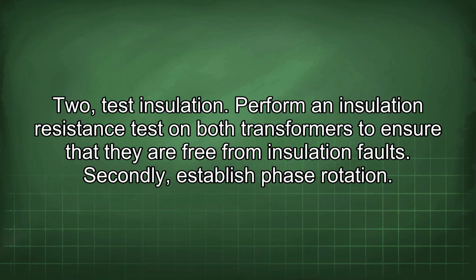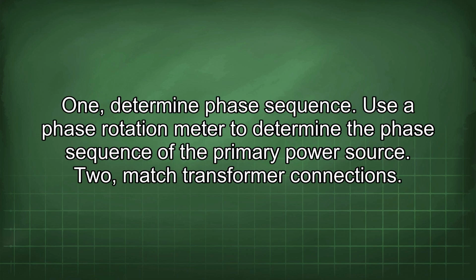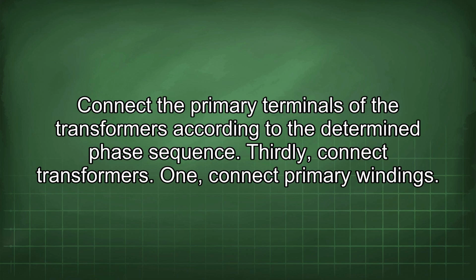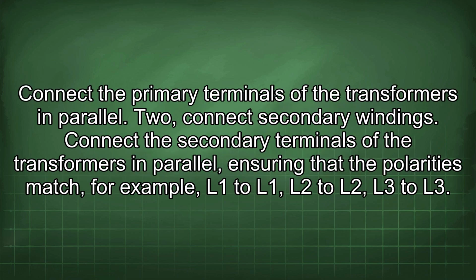Secondly, establish phase rotation. 1. Determine phase sequence. Use a phase rotation meter to determine the phase sequence of the primary power source. 2. Match transformer connections. Connect the primary terminals of the transformers according to the determined phase sequence. Thirdly, connect transformers. 1. Connect primary windings. Connect the primary terminals of the transformers in parallel. 2. Connect secondary windings. Connect the secondary terminals of the transformers in parallel, ensuring that the polarities match, for example, L1 to L1, L2 to L2, L3 to L3.